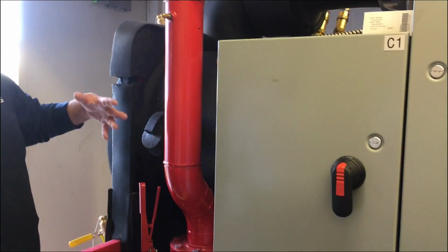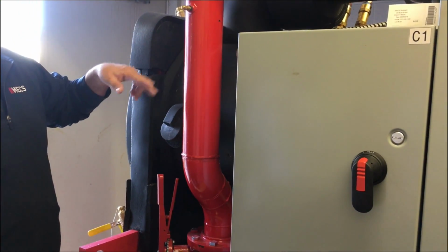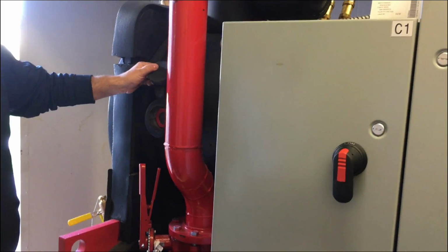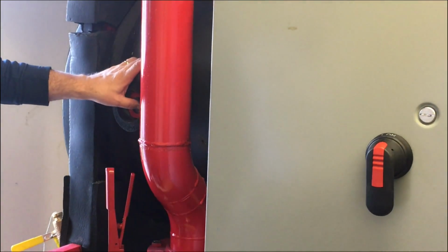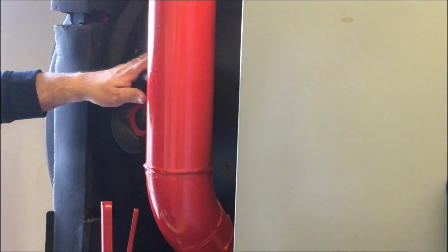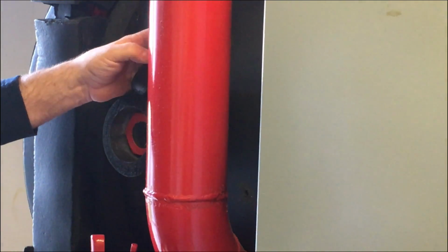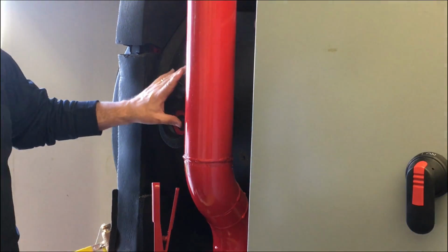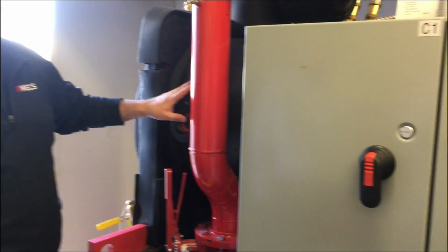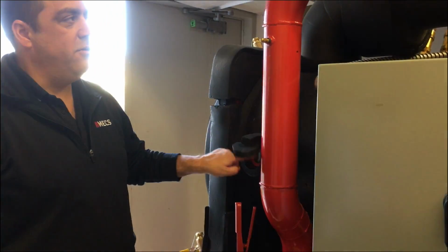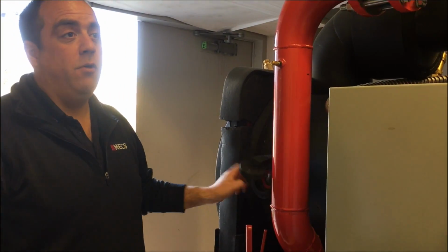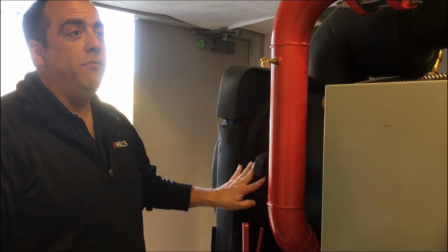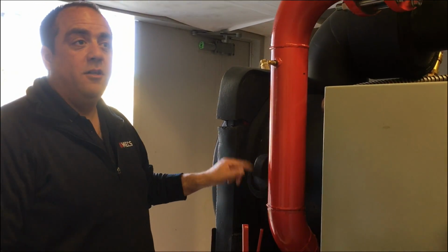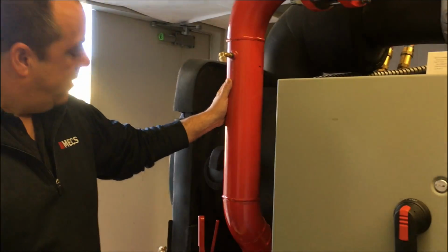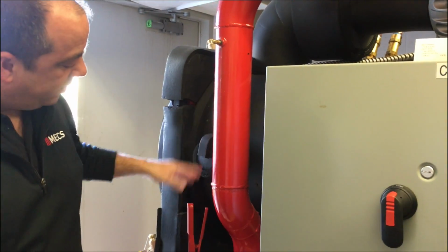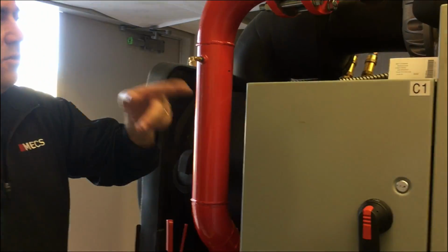So at 70% demand with both compressors running or greater, typically we'll see refrigerant in this glass while it runs. But if it's got no load on it, like a day like today, and we're running at minimum and cycling on, cycling off, you probably won't see any refrigerant in this glass. You will be cooling, but don't focus too heavy on that unless you're really running hard. If you're running hard and you're not making temp, then we're going to start looking at things like that. But what controls the levels on the other side, we'll talk about after we talk about this guy.